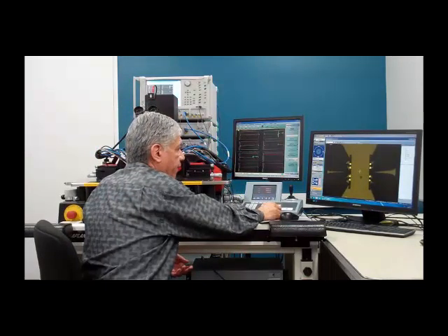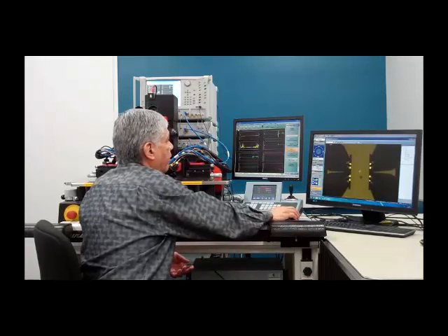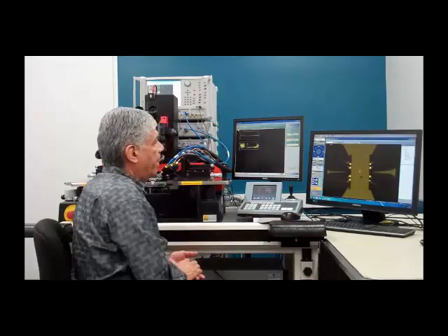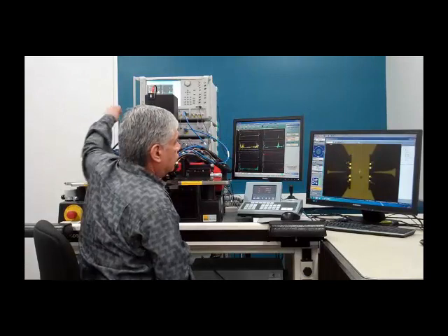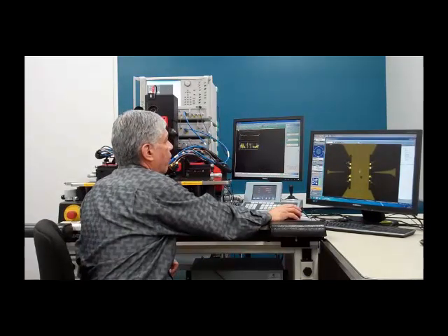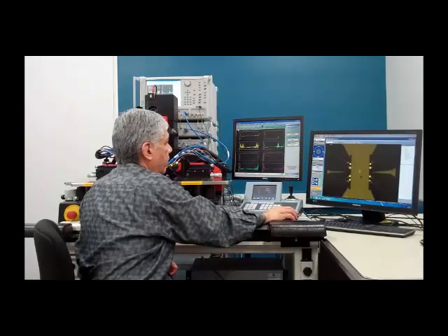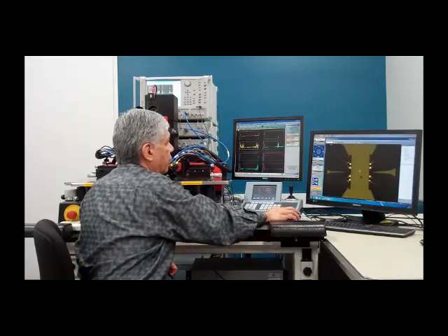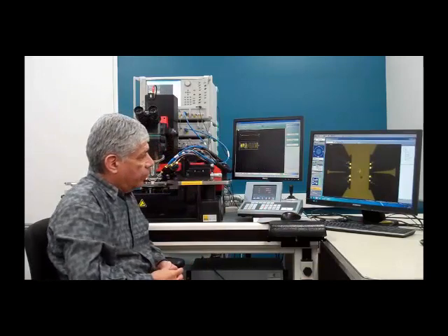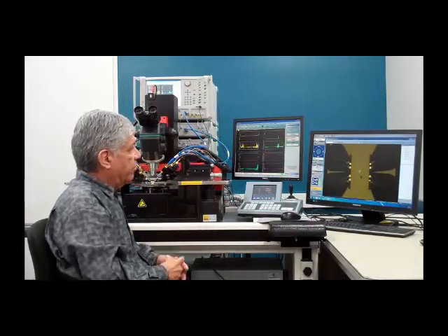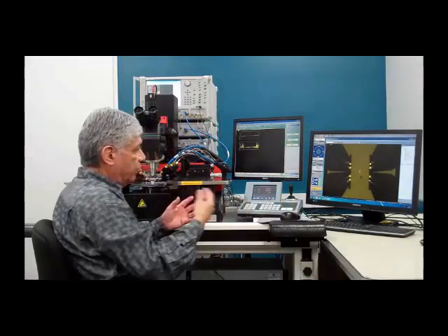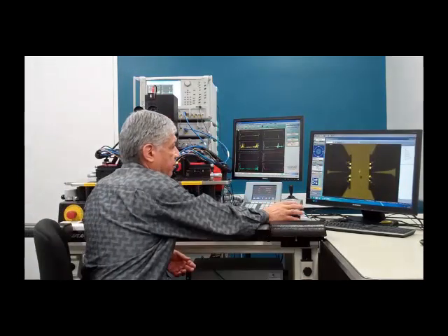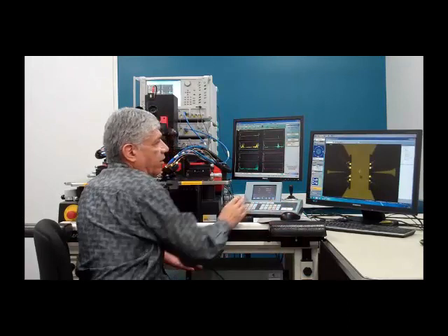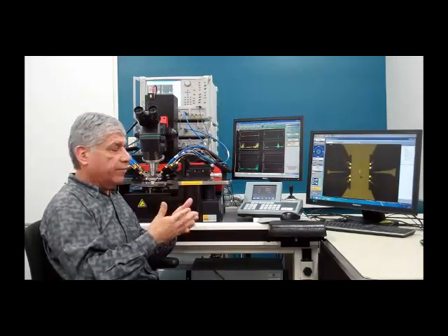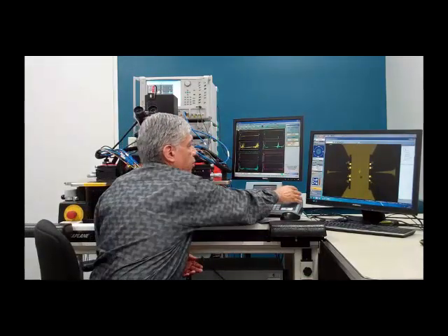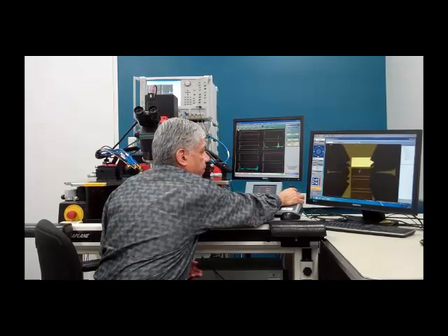Touch down on that and go in and perform our match measurements. And these are for ports 1 and 4. And now we go to ports 2 and 3. And since we've touched down on the two standards simultaneously, we can just go right through to the two different differential ports to make the measurements at the same time. Okay, so now all that's left is to measure our line, our through line. And so now I'll position over to the through standard right here.